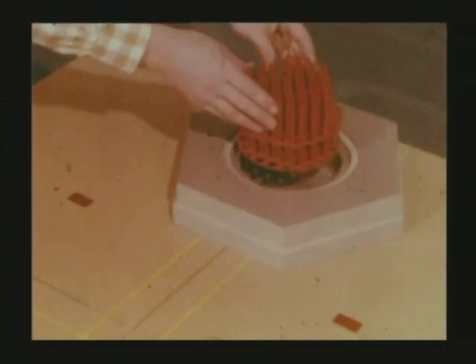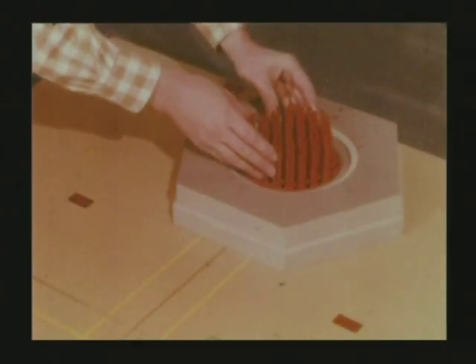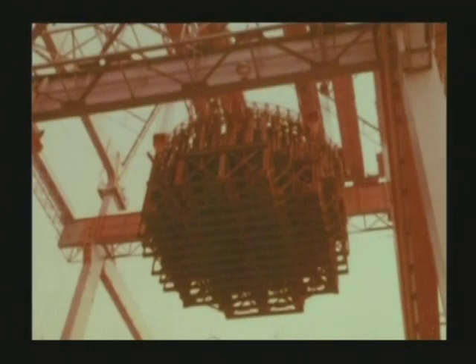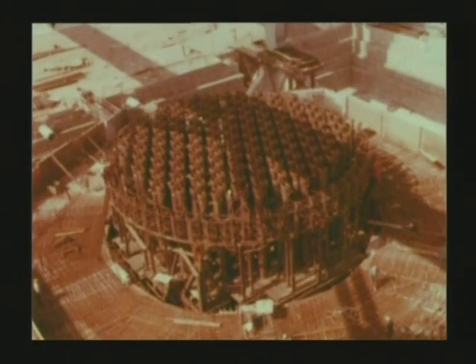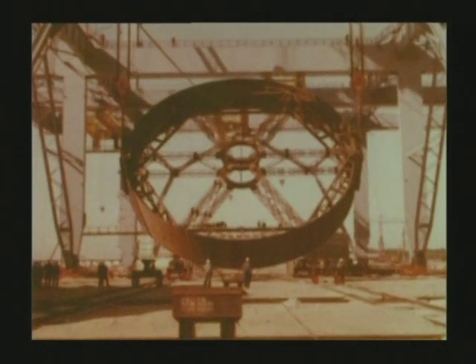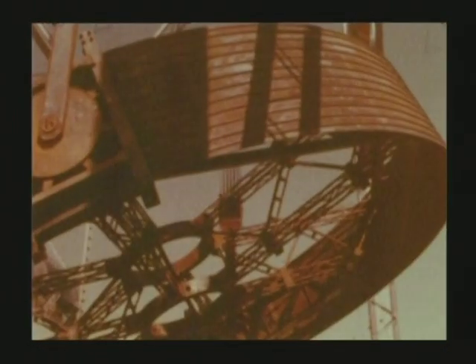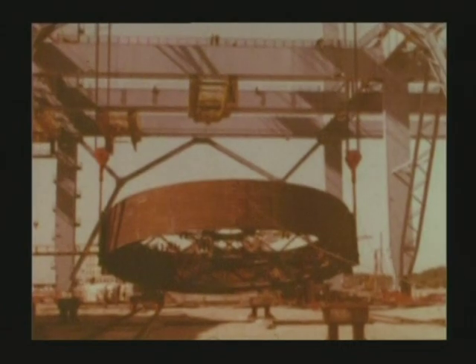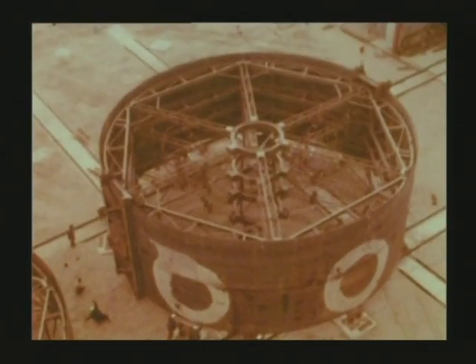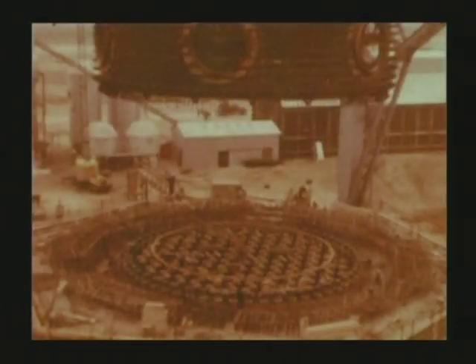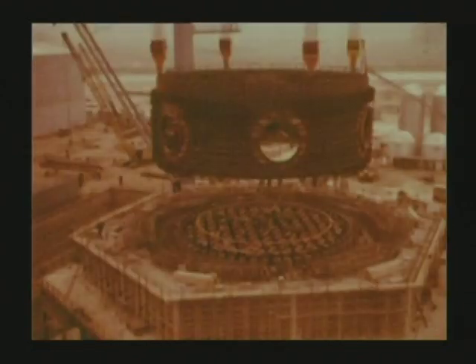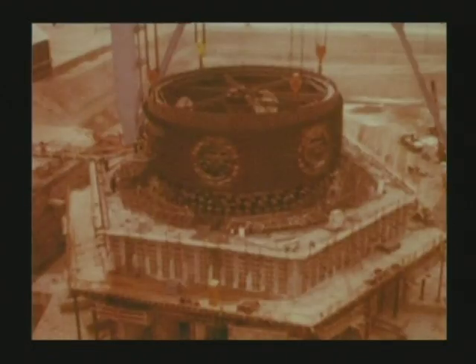These star-shaped piers are to support the reactor vessel, whose first component, manufactured on the site, is the lower tubular section, which contains all the water, steam, and instrument entry and exit tubes. On top of this tubular section, sheet metal shell rings are going to be placed in position. They are temporarily cross-braced to ensure rigidity during handling operations and concrete casting. Apertures are provided in the lower ring for the blowers and means of access. These rings, superimposed and welded to one another, will form a drum-shaped shell, making the vessel leak-proof.